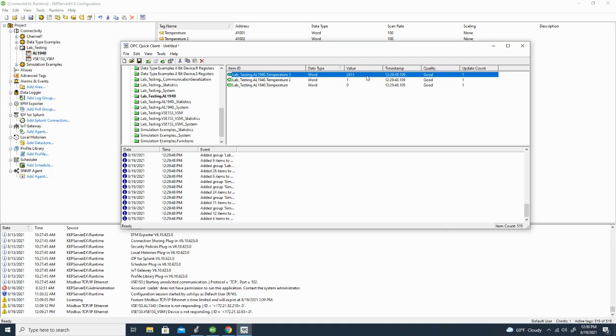is where I'm seeing my value. It says it's good. It's at 2415, 2413, and see, that's the issue. So I know this is the IO-Link data coming in, and I know that based off of the IODD PDF document that the structure of it is 2 bytes, and that's coming in as a default. So I can see the values as I increase the temperature change there.